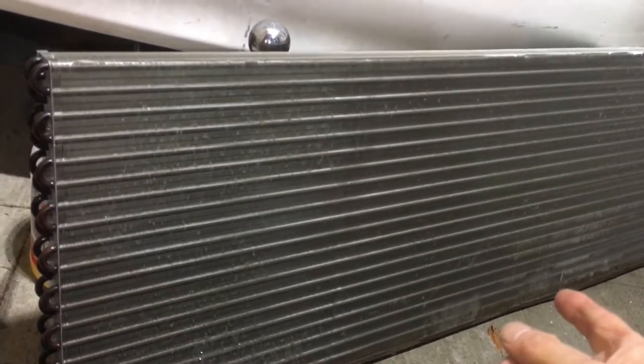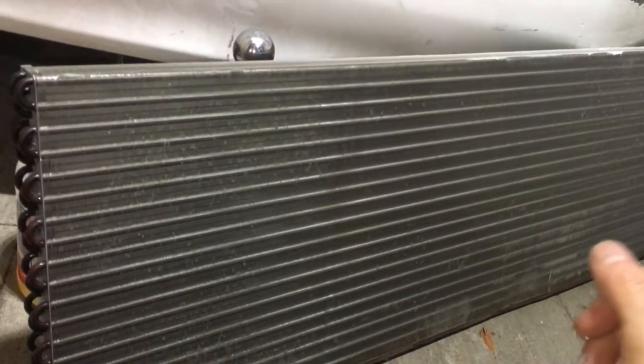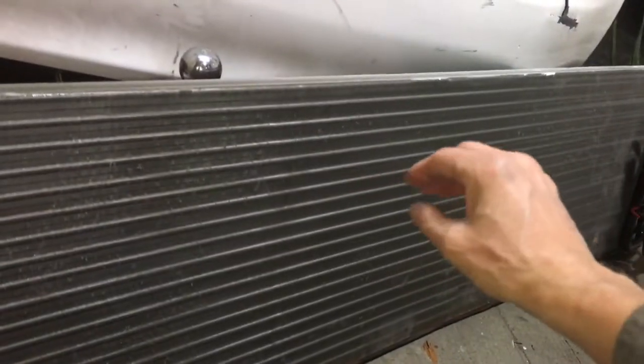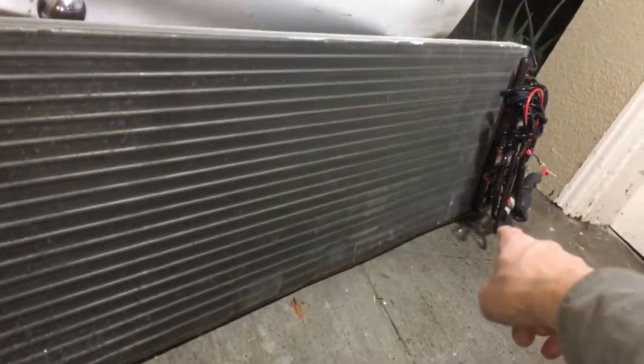This evaporator was exposed to corrosive chemicals — massive amounts of sulfur, chlorine bleach, and other cleaning and sterilization chemicals. It developed a leak way down at the very bottom row, the very last tube that stays wet all the time, where all the accumulated chemicals settle as condensate drips down. The leak happened right in the corner at the junction point where the steel galvanized plate, the aluminum, and the copper all come together — that's where all the salts and chemicals concentrated and caused the leak.